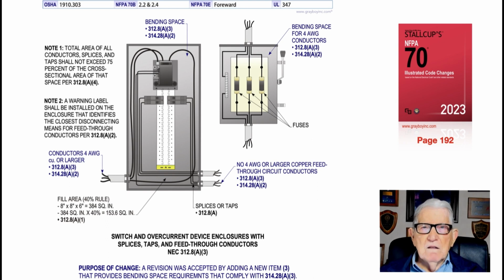And to obtain these bends for gutter space, terminations, and so forth, we see our tables 312.6(A) and (B)(2) that would give us wire bending inches and so forth that we would have to have for terminating conductors, either for S, L, or Z bend. Now, on page 192 of the NEC is where you can pick up these rules. And one illustration, sometimes we do not list the page number because we want you to look it up and get used to using the book. But basically, that's what this rule is all about. It's just addressing bending space when you have an S, L, or Z bend.